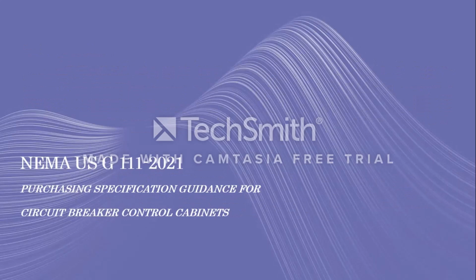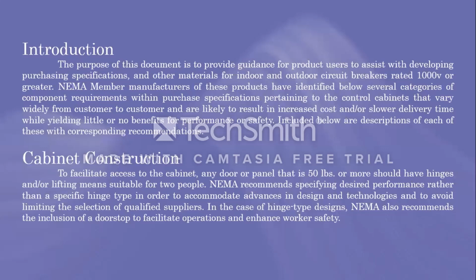So, introduction to circuit breaker control cabinets. The purpose of this document is to provide guidance for product users to assist with developing purchasing specifications and other materials for indoor and outdoor circuit breakers rated 1,000 volts or greater. NEMA members, manufacturers of these products, have identified below several categories of component requirements within purchase specifications pertaining to the control cabinets that vary widely from customer to customer and are likely to result in increased cost and or slower delivery time while yielding little or no benefits for performance or safety. Included below are the descriptions of each of these with corresponding recommendations.